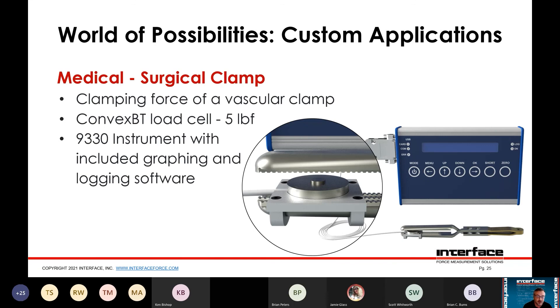This is an interesting application for a medical customer wanting to test a vascular clamp — they needed to understand the force supplied by the clamp. We fabricated a small fixture paired with our new convex BT load cell, a very low-capacity one. Basically the load cell is being compressed in the clamp. The fixture was designed to hit a certain height because the test needed to be done at a specific closure distance of the clamp. It's hooked up to our 9330 instrument, which has software for graphing and logging and can also log to an SD card for viewing data on the computer.